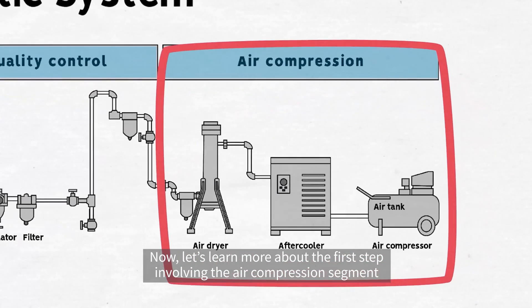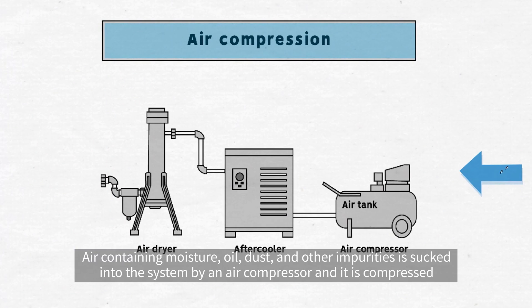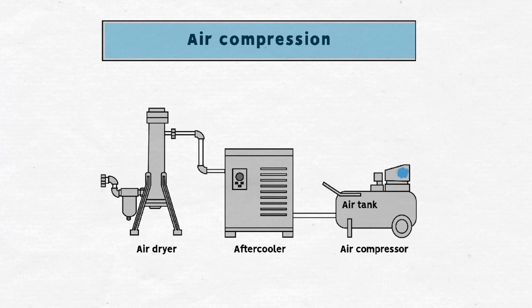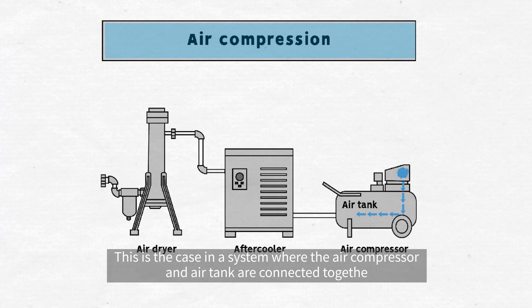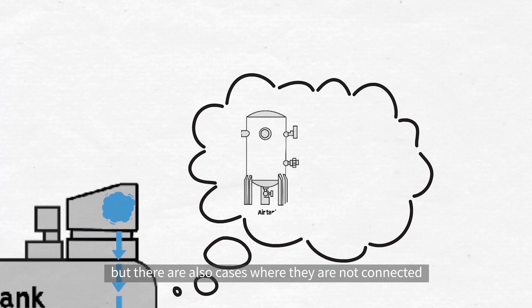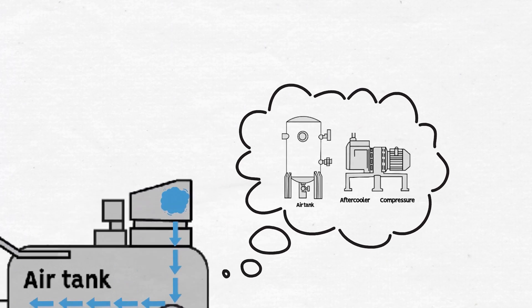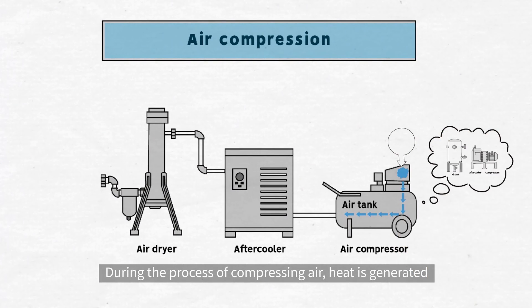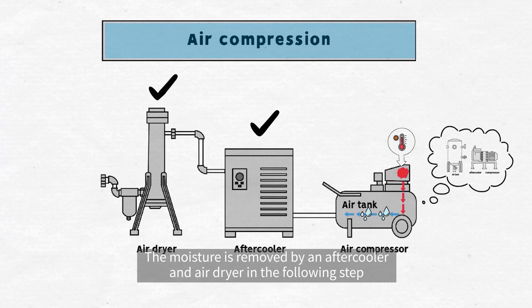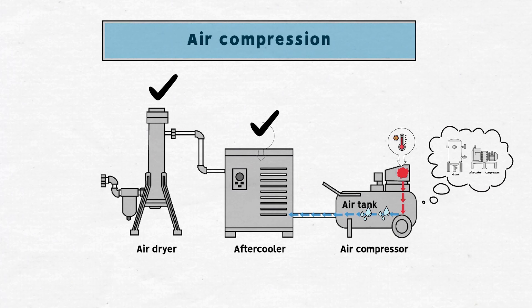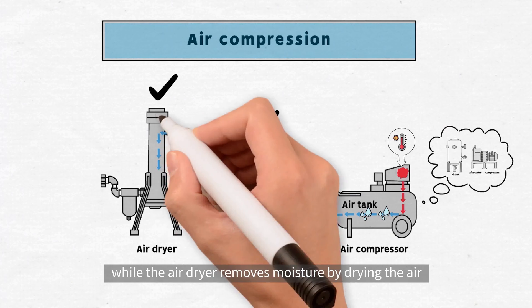Now let's learn more about the first step involving the air compression segment. Air containing moisture, oil, dust and other impurities is sucked into the system by an air compressor and it is compressed. The compressed air then enters an air tank where it is stored. This is the case in a system where the air compressor and air tank are connected together, but there are also cases where they are not connected. During the process of compressing air, heat is generated. As the heat is conveyed through a pipe, it cools down and this creates moisture in the air. The moisture is removed by an after cooler and air dryer in the following step. The after cooler removes moisture by cooling the air, while the air dryer removes moisture by drying the air.